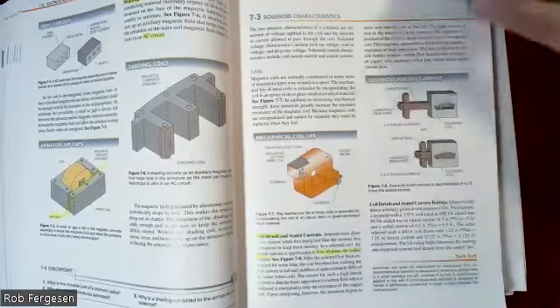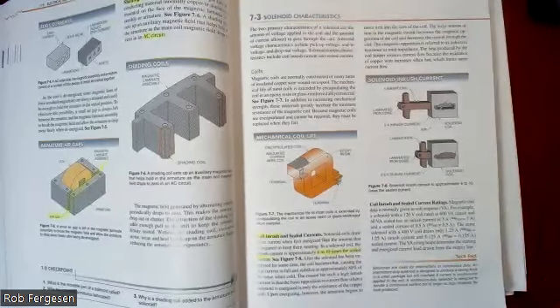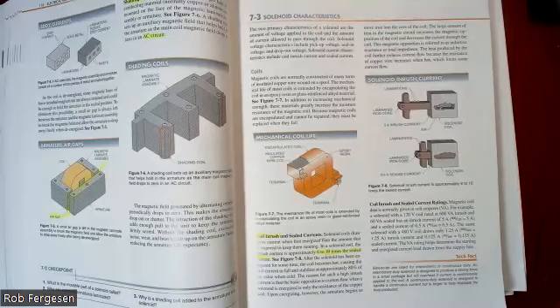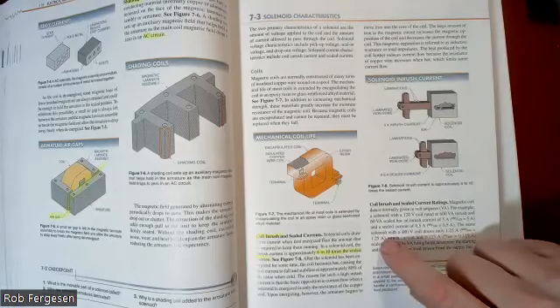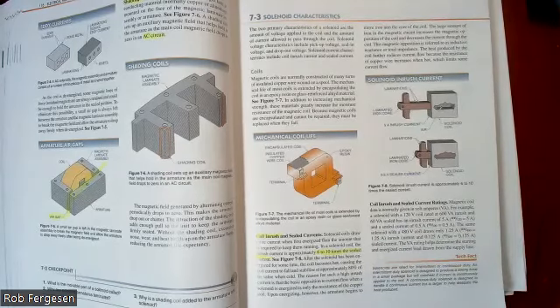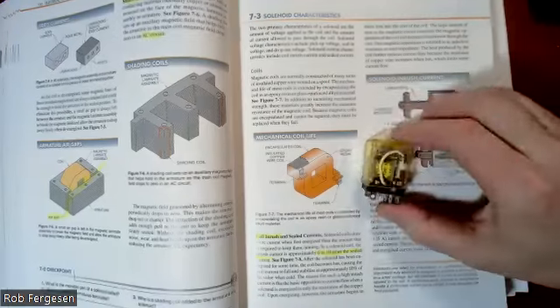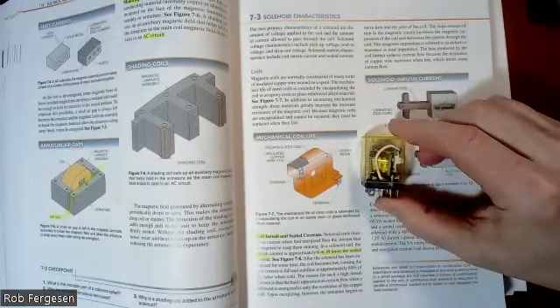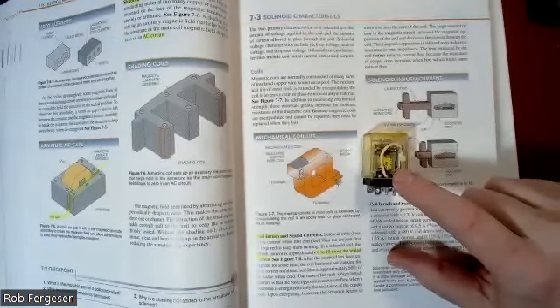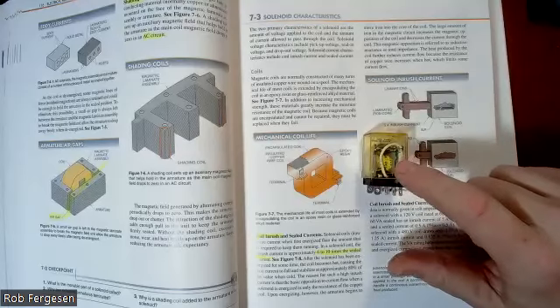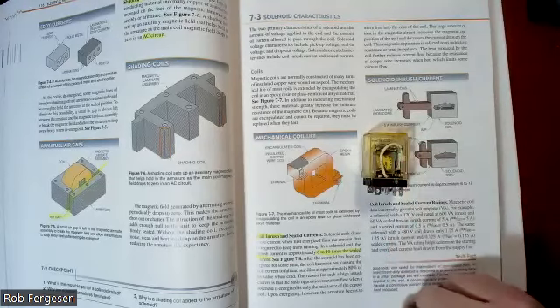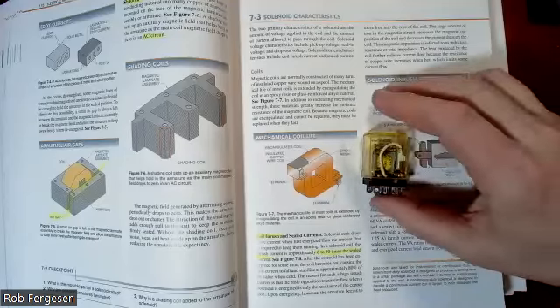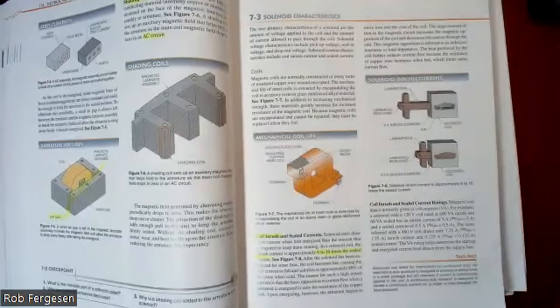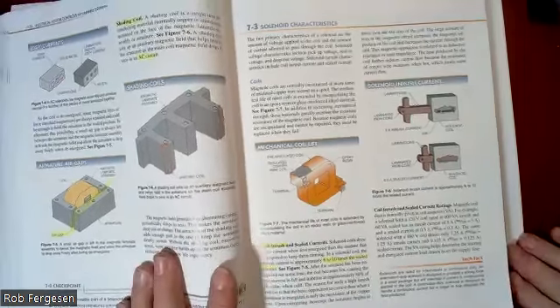So this is a classic example of weird problems that occur in automated systems that are associated with motors and also contactors. And sometimes even smaller relays like this, though that's pretty unusual, a little DC relay. Sometimes even smaller relays like this will cause a little bit of an inrush, and you'll get that weird bump of static on your sensors, and they'll cause a problem.